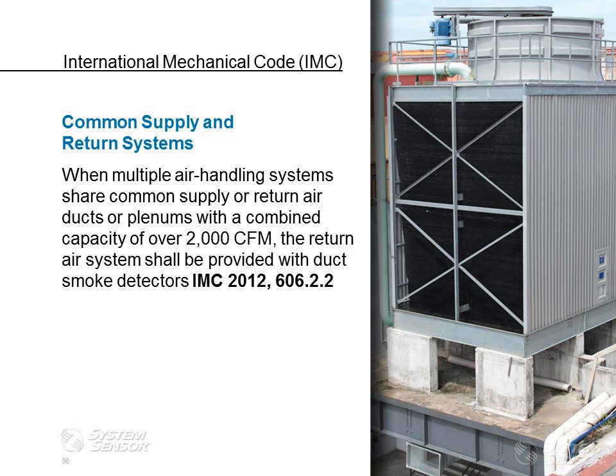The difference here is when it's a common supply or return, a lot of buildings now are going to smaller units. So the individual unit may not be 5 ton or larger. It may be smaller than 2,000 CFM. But if you have 4 units and the combined capacity is greater than 2,000 CFM, then you still have to include duct smoke detectors. You can't substitute multiple small units in place of one large unit and get away with not putting in the duct detectors. They're looking at the combined capacity of the space.